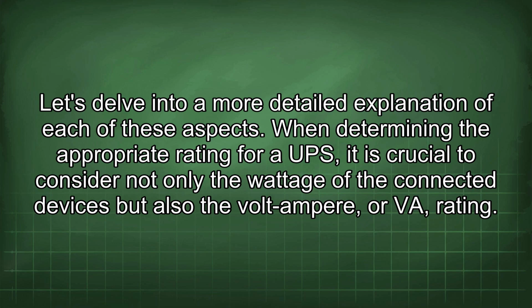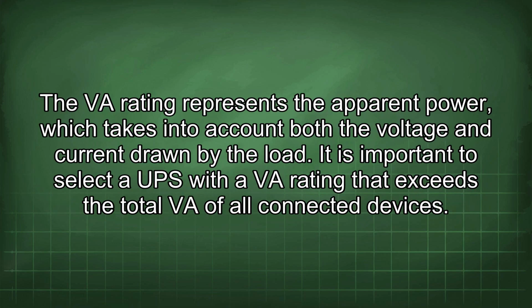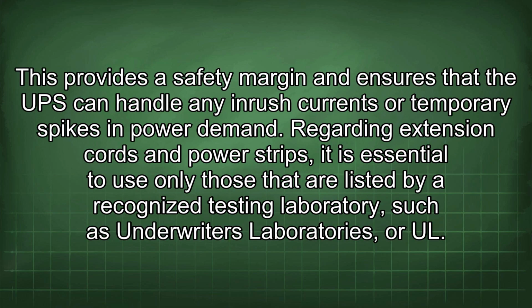When determining the appropriate rating for a UPS, it is crucial to consider not only the wattage of the connected devices but also the volt-ampere, or VA, rating. The VA rating represents the apparent power, which takes into account both the voltage and current drawn by the load. It is important to select a UPS with a VA rating that exceeds the total VA of all connected devices. This provides a safety margin and ensures that the UPS can handle any inrush currents or temporary spikes in power demand.